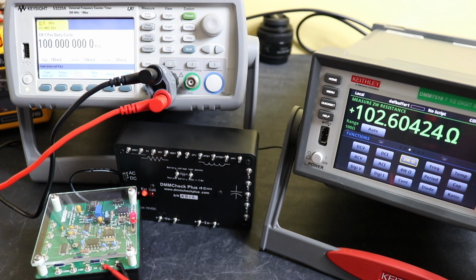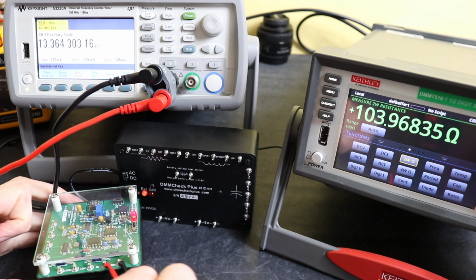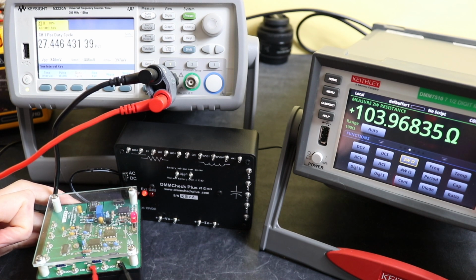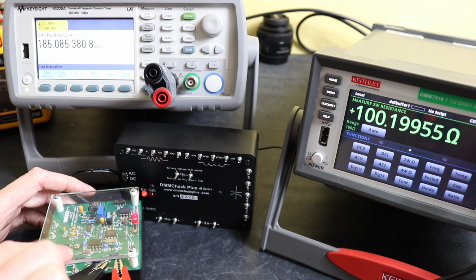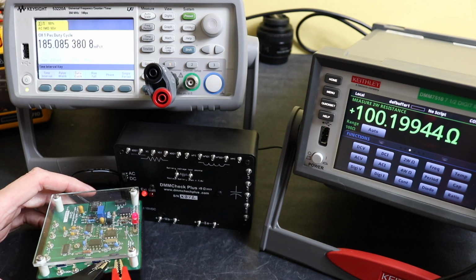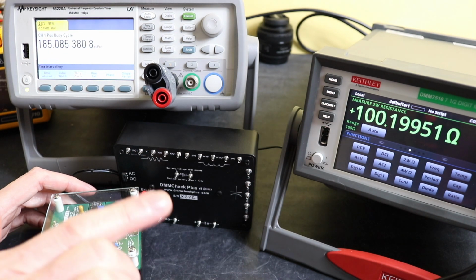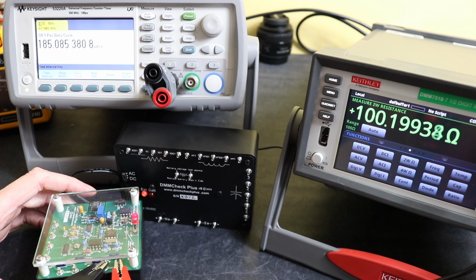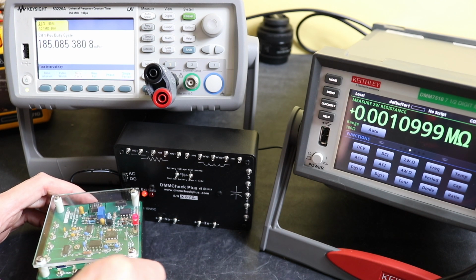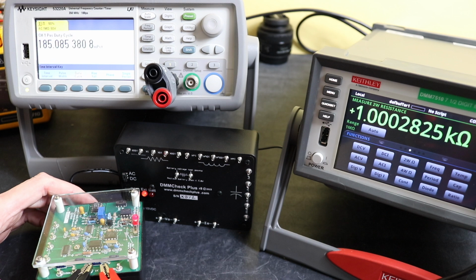Okay, so we flipped over to resistance measurements, two wire on this. We are reading 102 ohms there on the Keithley. It's quite high, isn't it? Okay, so we've just swapped the leads over, changed the leads out, and we've got a bit better measurement. So we'll do the resistance measurements with these leads. We've got 100.19 now on the 100 ohm resistor.